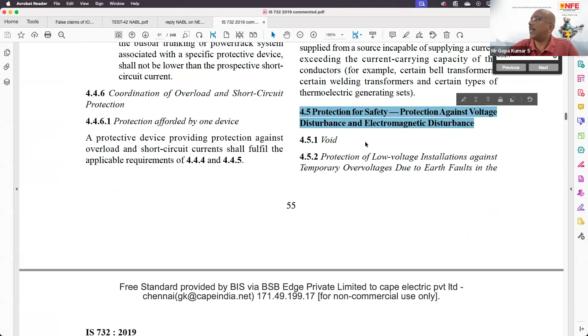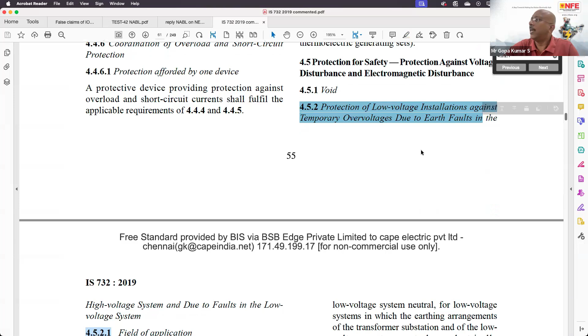Okay. The 4.5.2.1 talks about protection for safety, protection against voltage disturbances and electromagnetic disturbances. It talks about protection of low voltage installation against TOV due to earth fault in the high voltage system, due to fault in low voltage and due to fault in. So basically this clause is talking about how to protect an electrical installation when there is a fault on the high voltage side of the electrical installation. So it consists of various measures, how you should install the transformer, whether it is TN system, TT system, and so on.